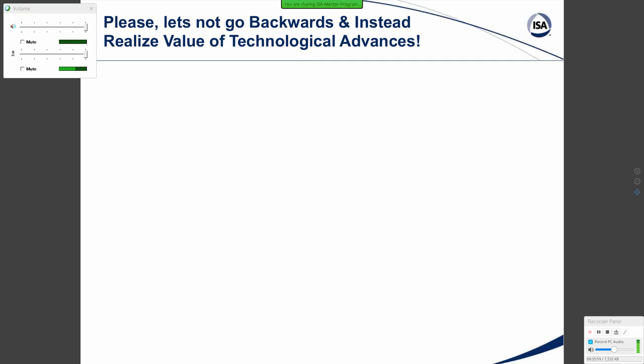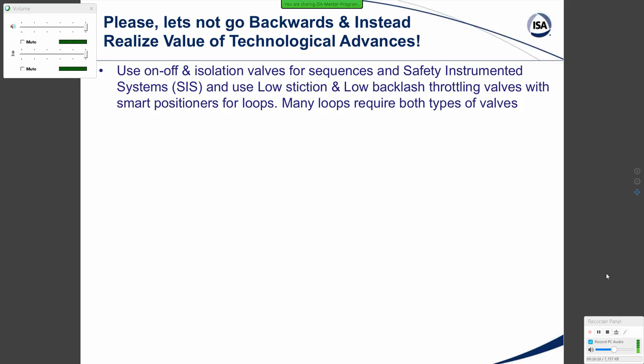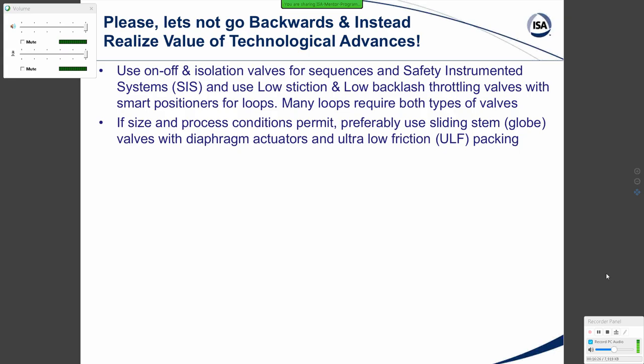Please, let's not go backwards — instead realize the value of technology and the advances made in the design of real throttling valves. Use on-off and isolation valves for sequences and safety instrument systems (SIS), and use low-friction, low-stiction, low-backlash throttling valves with smart positioners for loops. Many loops require both types of valves. If size and process conditions permit, preferably use sliding-stem globe valves — there is essentially no backlash with diaphragm actuators, which are very sensitive, and ultra-low-friction (ULF) packing minimizes stiction. A sliding-stem globe valve designed for throttling will not have excessive friction near the closed position.